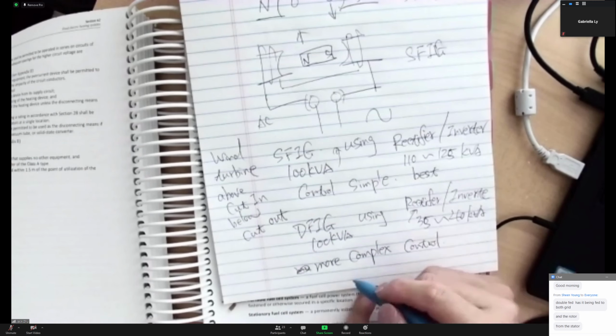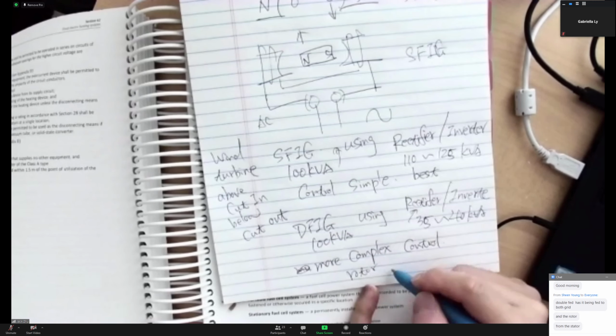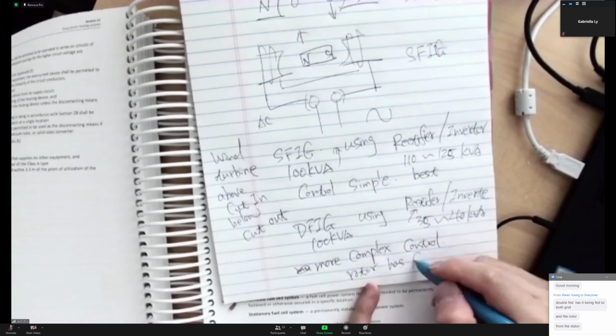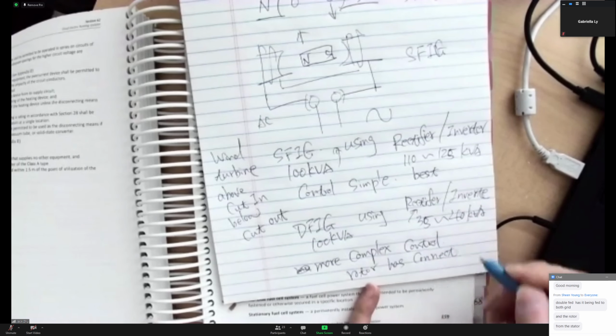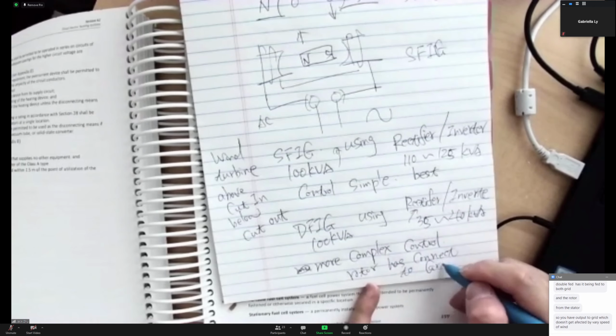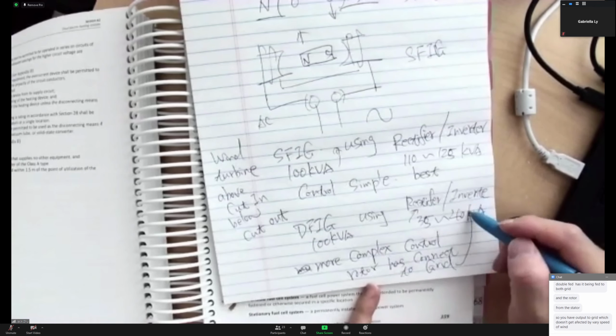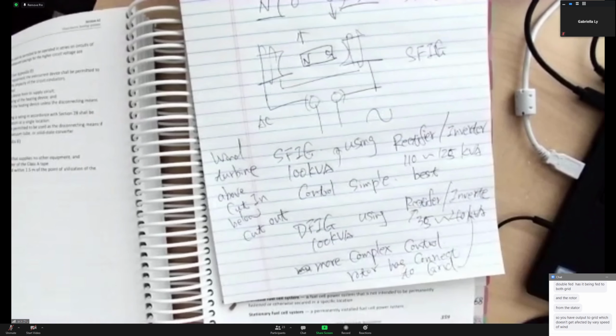Your rotor has the connection to the grid, but it's through this rectifier and inverter. So you generate the voltage on the stator. At the same time, the stator is going to feed the grid, and you're going to take that power, change it into different frequency, different voltage, and feed it back into the rotor to match whatever the wind speed is.